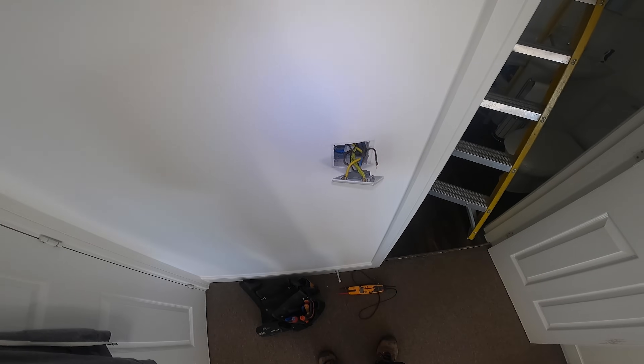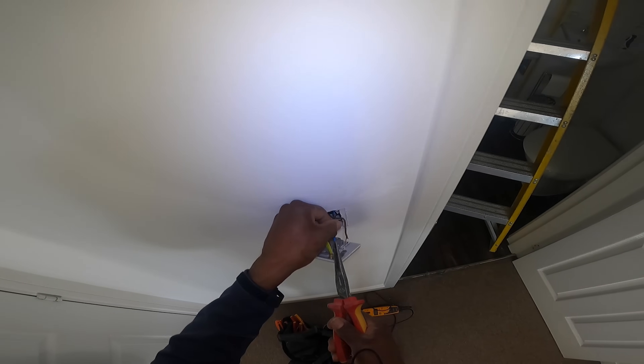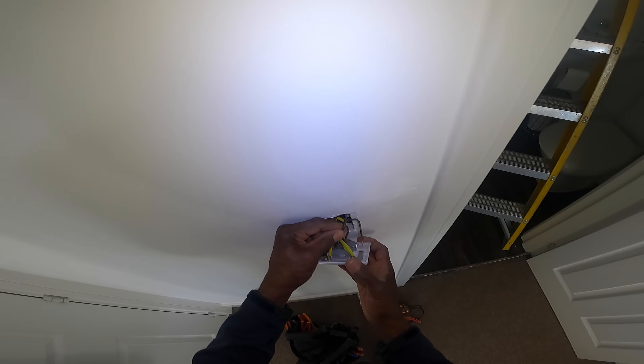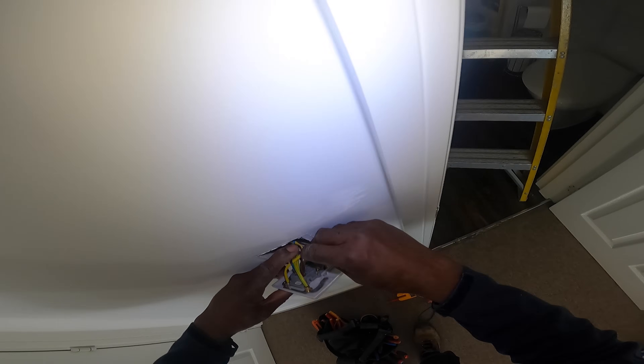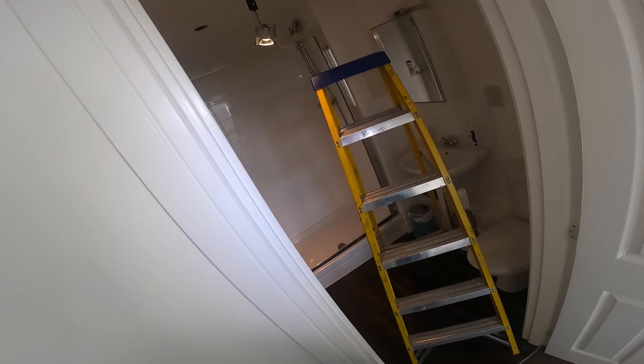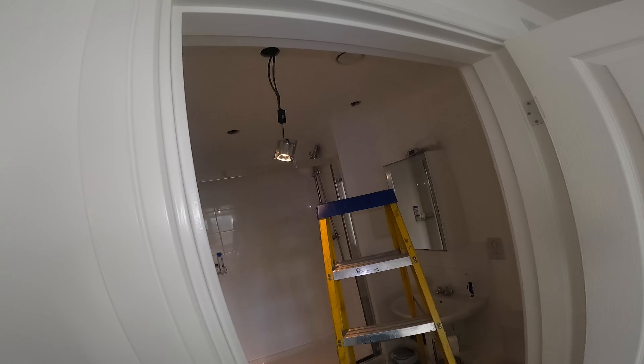That shouldn't be happening. This is the switch here, yeah? Why they've used a double pole switch I'm not sure. So when I switch it on, it's not coming on. What I'm going to do is disconnect it and put it straight across the top part, because there's no neutral here. Right, lights are coming on. See that? Lights are on. So it's a dodgy switch.